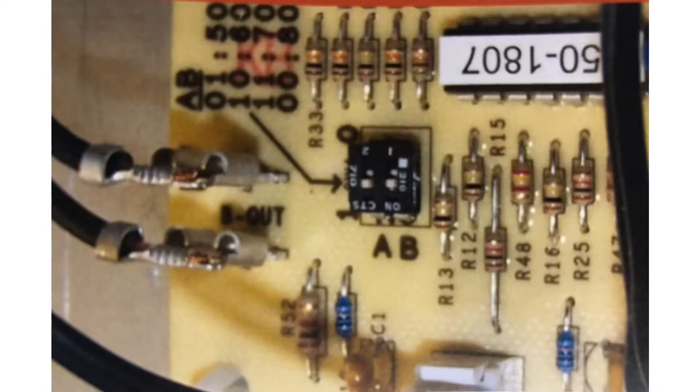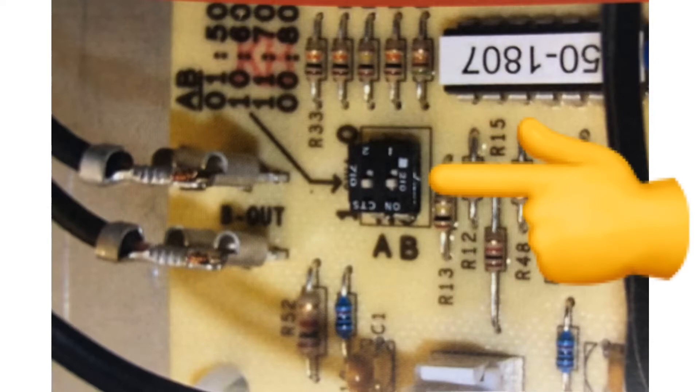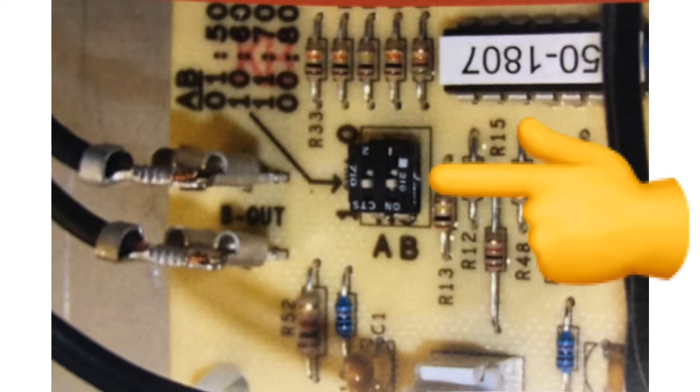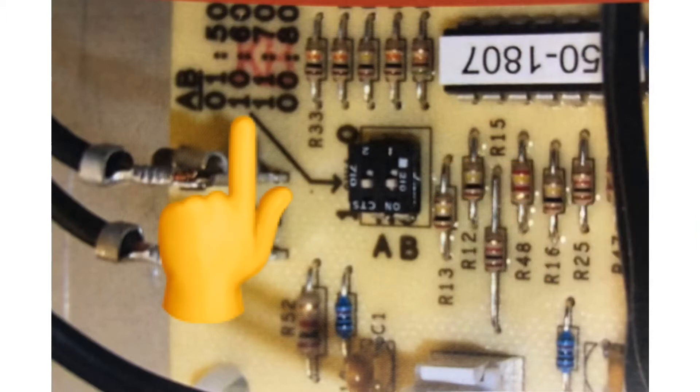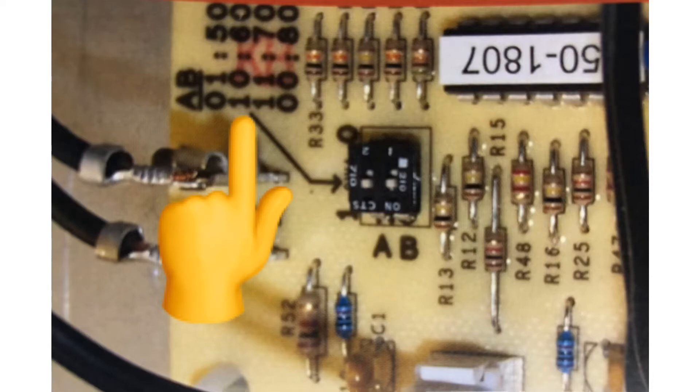All right, one more thing I want to point out on this board here since we're talking about our sensors. Our coil sensor does have a defrost termination temperature. Once this board sees that it will stop defrost cycle. Now the dip switch is here on the board. You can set that temperature depending on where you're at in the country. Pretty simple. Two dip switch here. We have the different temperatures you can set it for: 50, 60, 70, and 80.